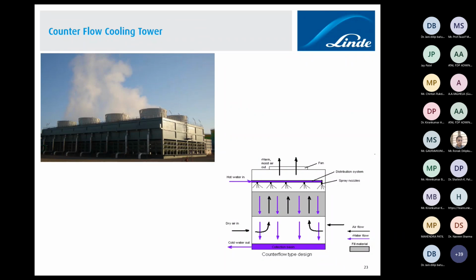Absolutely correct. And Dr. Jani, most of the time, let us look at even this mechanical cooling tower. You can say twin cell, so there are 8 cells in this cooling tower. Usually when we design mechanical fans, we always keep both a hydraulic margin on the flow and a margin equivalent to one cell for heat load, in terms of humidity variation and variation in wet bulb temperature throughout the season. So by operating, I would say, 7 fans, we would be able to achieve the delta T range.